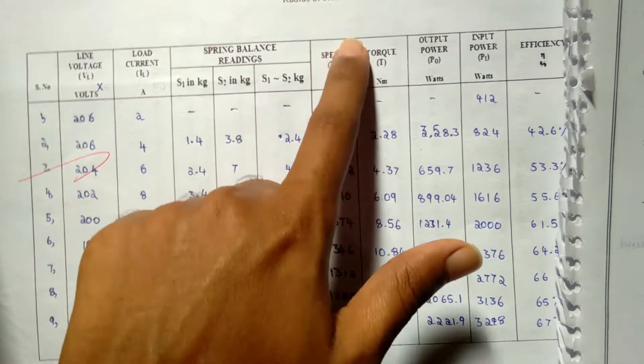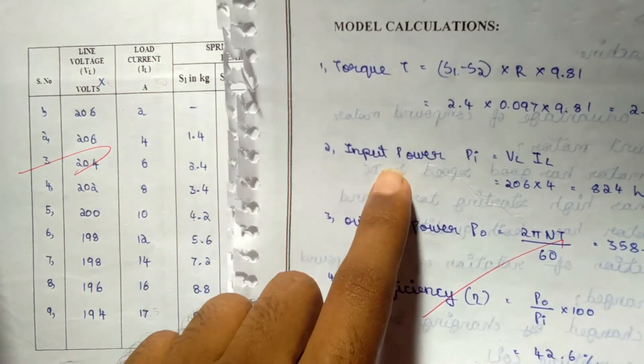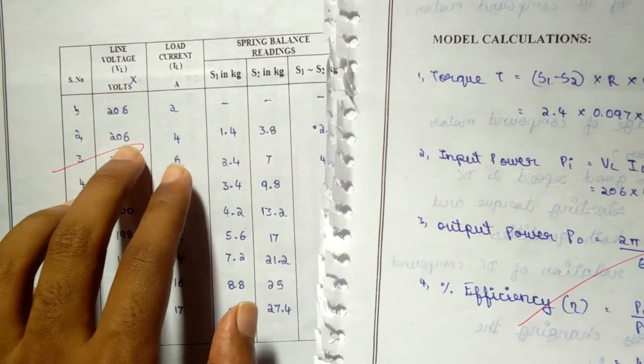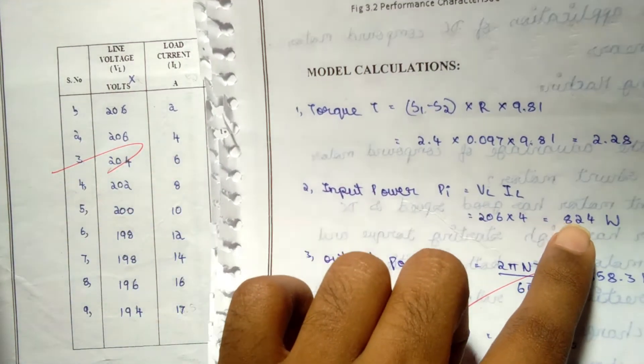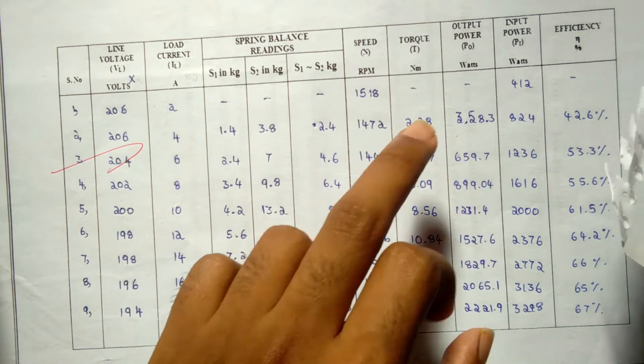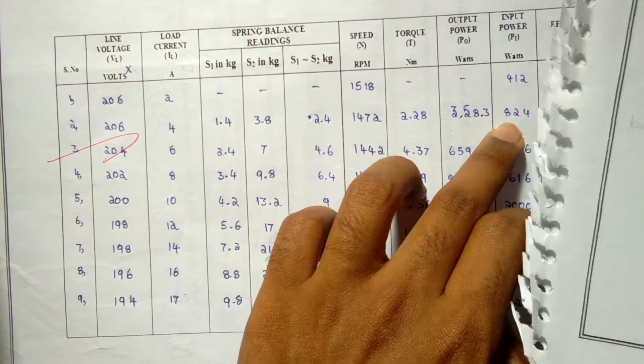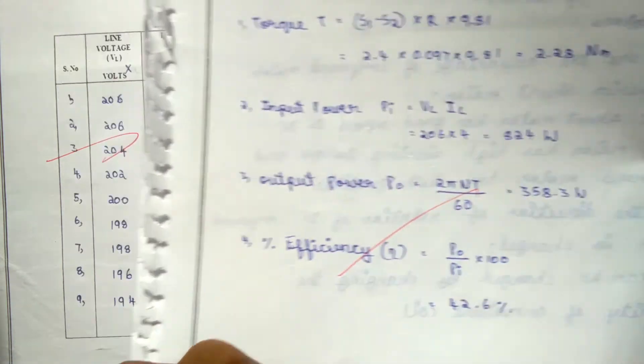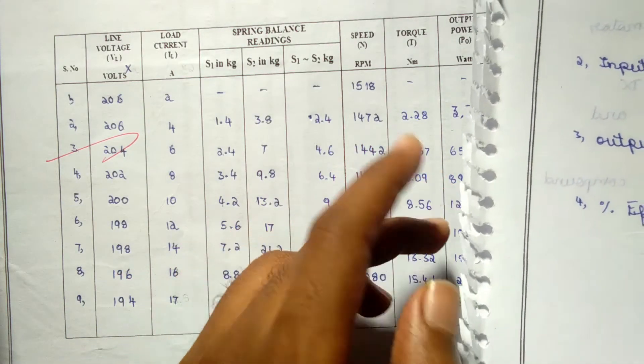The torque, and then input power Pi = VL × IL, VL × IL, 824 watts. And then output power Po = 2πNT/60. After substituting these values, the output power will be 358.3 watts.